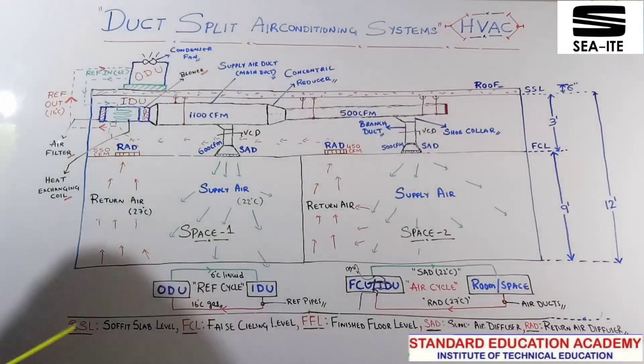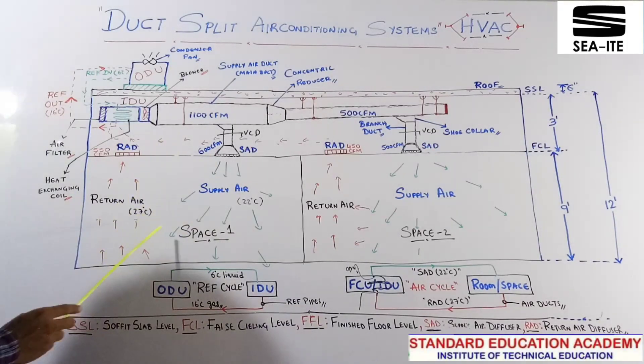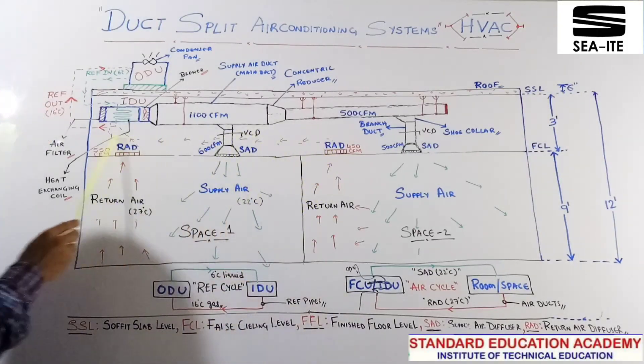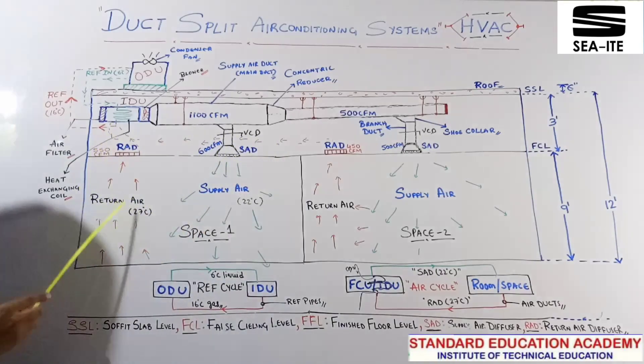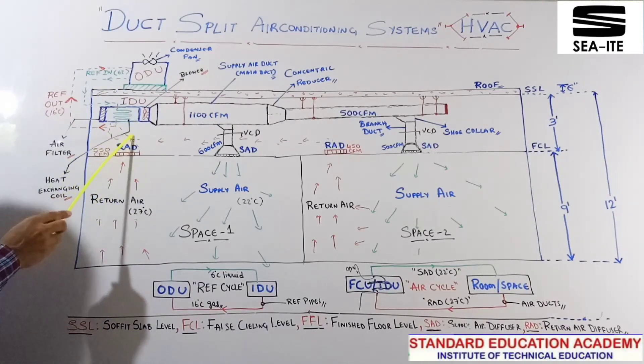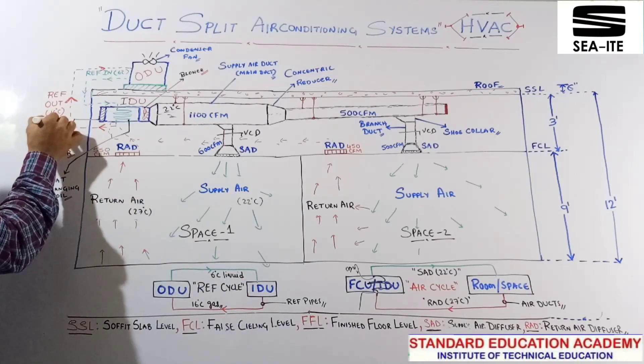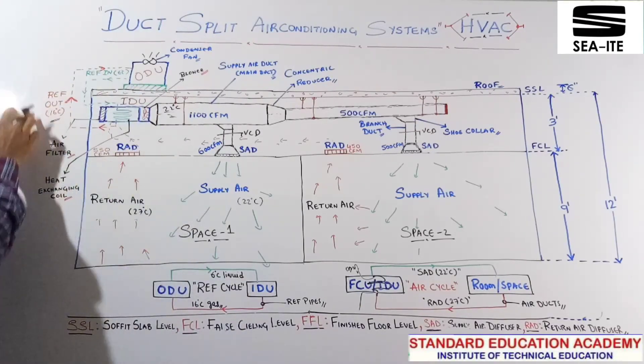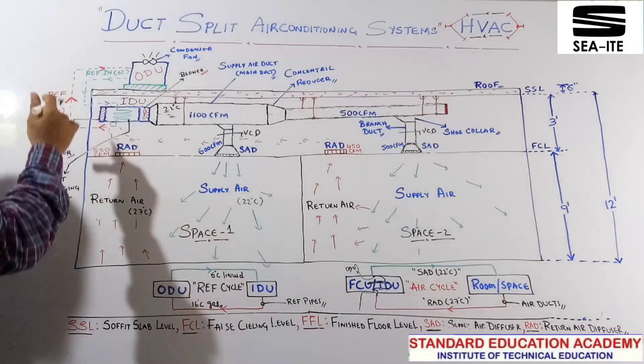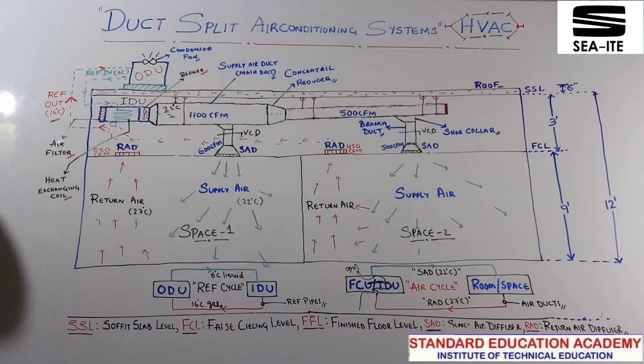From outdoor to indoor, refrigerant at 6 degree Celsius is coming. The return air, which is striking at 27 degree Celsius from the return air diffuser, is sucked in by the blower. Return air temperature 27 degree Celsius, refrigerant temperature 6 degree Celsius — heat exchange is taking place. Due to that you are getting a supply air of 22 degree Celsius. But your refrigerant outlet, whose inlet is 6 degree liquid, gives you 16 degree condensate gas at outlet. Again this gas is going to your outdoor unit to carry out the cycle, to get converted back into 6 degree refrigerant.